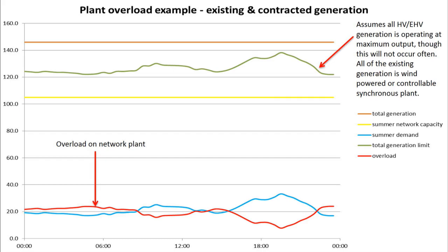So the total generation installed capacity is 146 megawatts, and that's represented by the brown line at the top here. We've just left that static. So that's effectively full generation export all day. This is one day, a day of summer minimum demand. The summer network capacity is down at 105 megawatts here, which is represented by the yellow line. The blue line represents the summer demand. You can see that fluctuating throughout the day. So that's the demand on the day of minimum demand during the year.